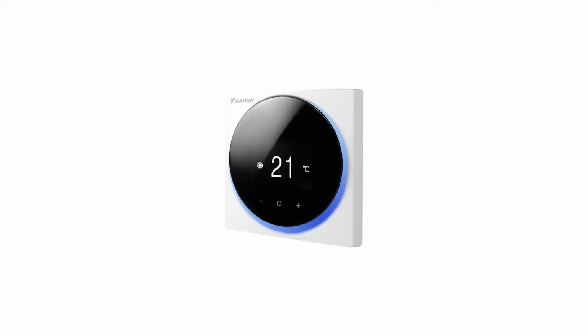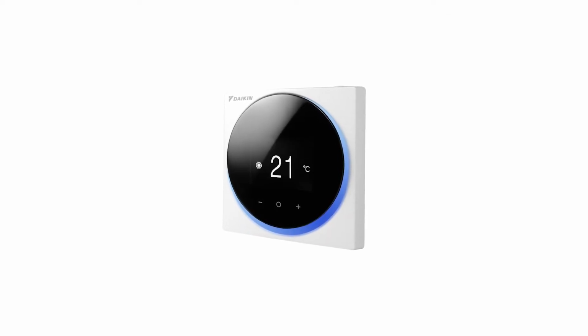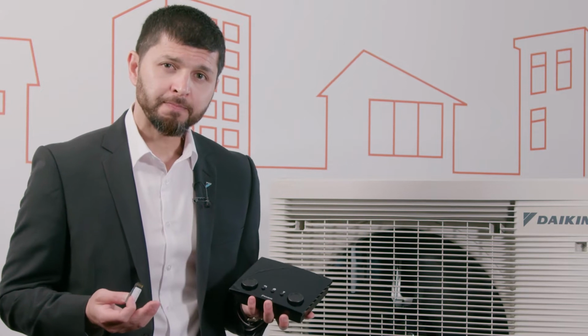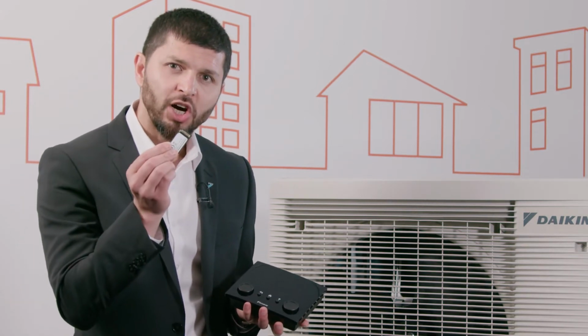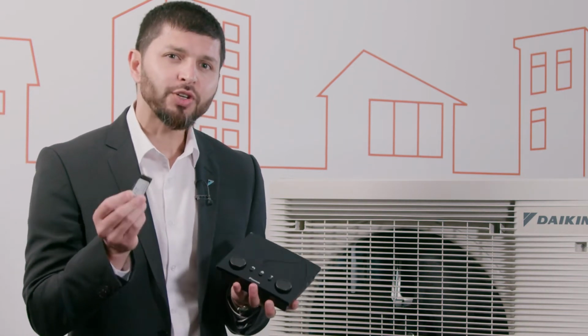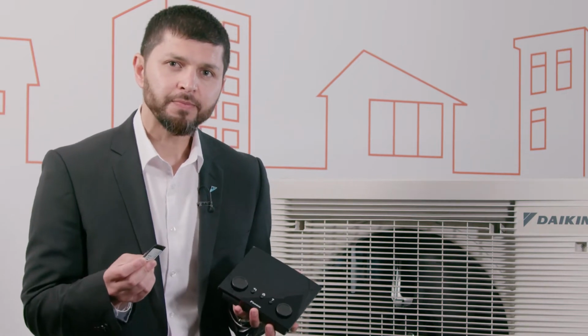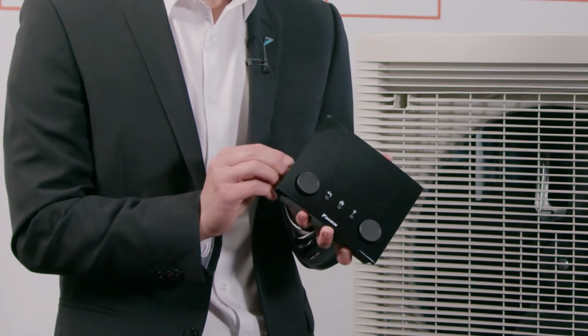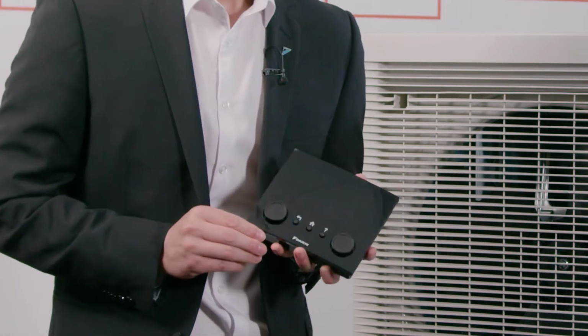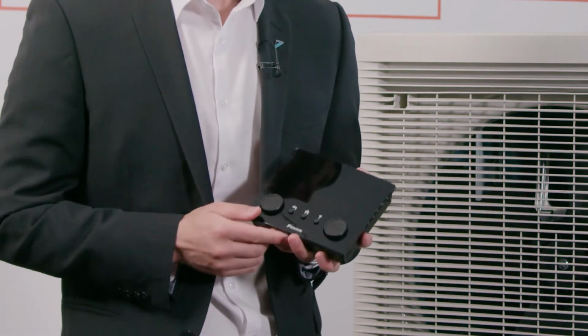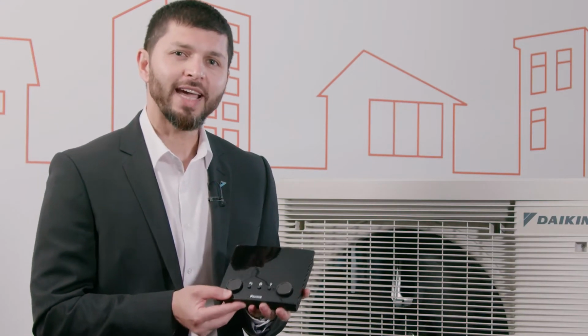Daikin Madoka thermostat or third-party thermostat, or both, can be used along with the user interface. The system is cloud ready with this wireless LAN cartridge or SD card supplied as a standard. Just take the SD card out of the bag delivered with the unit, slot it into the user interface, which is also supplied with the unit, and the system is ready to be controlled and monitored by the app.